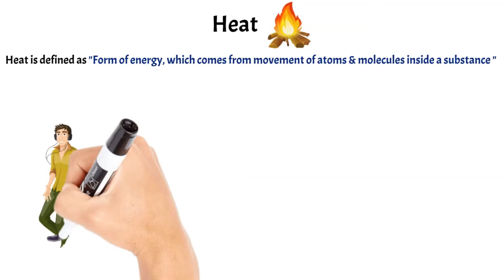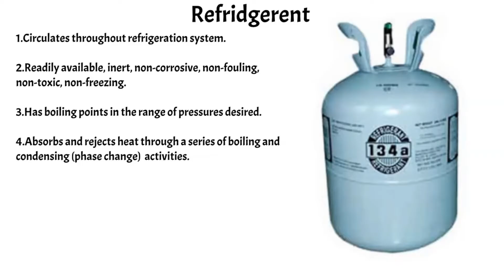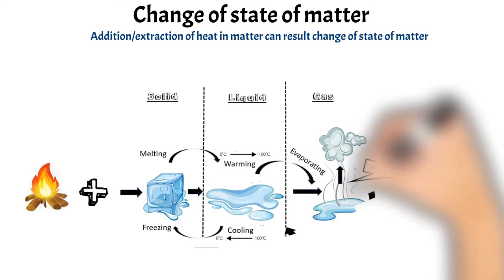Refrigerant. It circulates throughout the refrigeration system. Readily available, inert, non-corrosive, non-flammable, non-toxic, non-freezing. It has boiling point in the range of pressure desired. It absorbs and rejects the heat through a series of boiling and condensing activities. Pressure and temperature relationship. To increase or decrease the boiling point of a substance, we must alter the pressure on the substance. Increasing the pressure increases the boiling point. To decrease the boiling point, decrease the pressure. A good example is automotive cooling system. The pressure cap keeps the radiator from boiling over by increasing the pressure on the coolant. Addition or extraction of heat in matter can result change of state of matter. You can also watch the video of link given in description for more understanding on this topic.